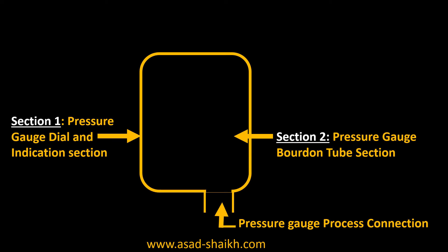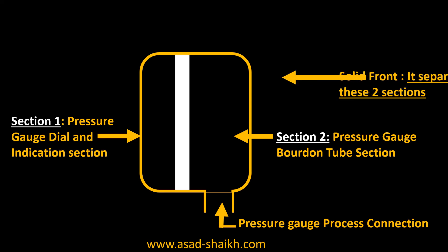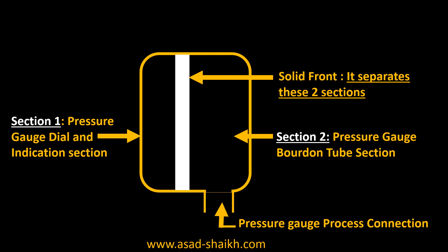So for such high pressure applications, we use the concept of solid front. As the name suggests, the solid front acts as a wall in between section 1 and section 2. This solid front separates these two sections such that the process fluid, in case of a hazard, would not enter into the dial gauge indication side.